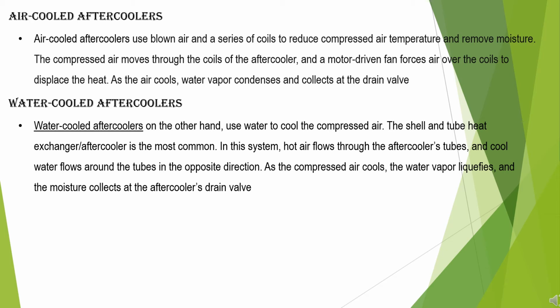Water-cooled aftercoolers. Water-cooled aftercoolers, on the other hand, use water to cool the compressed air. The shell and tube heat exchanger or aftercooler is most common. In this system, hot air flows through the aftercooler's tubes, and cool water flows around the tubes in the opposite direction. As the compressed air cools, the water vapor liquefies and the moisture collects at the aftercooler's drain valve.